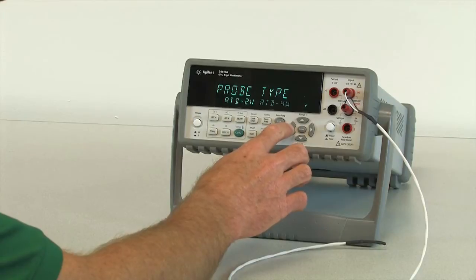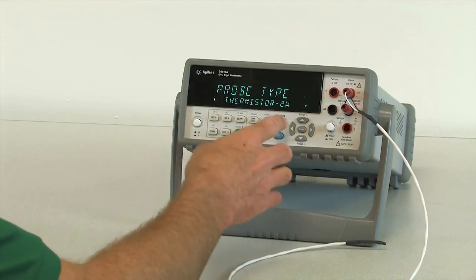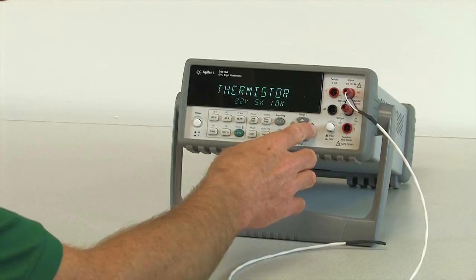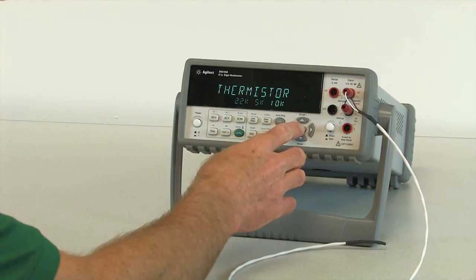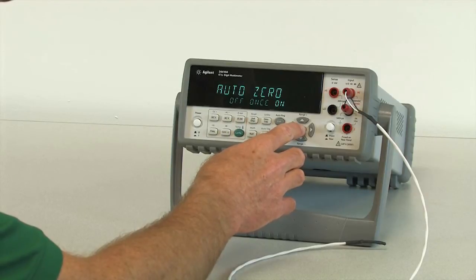As you can see, it can measure RTDs or thermistors. So I'm going to select a two-wire measurement for our thermistor. Then we need to select the value. This is a 10K thermistor, so I'll select 10K. I'm going to select the rest of the defaults for our measurement.